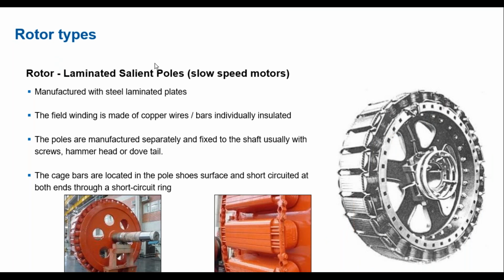This just gives a little bit more information on the construction of the salient poles. Essentially, the poles are separated, and you can see nicely on this photo here the squirrel cage or damper winding that's used only during startup of the machine is constructed on the outside surface of the pole shoes.